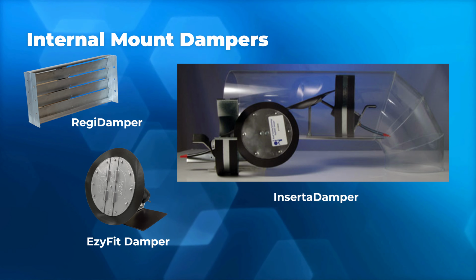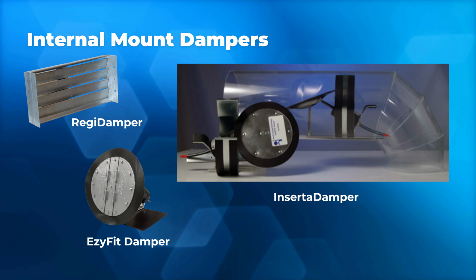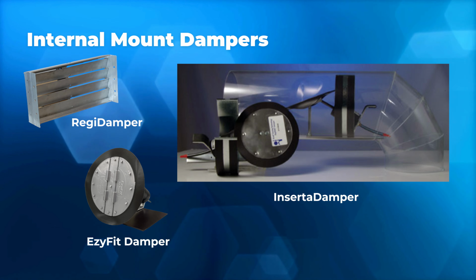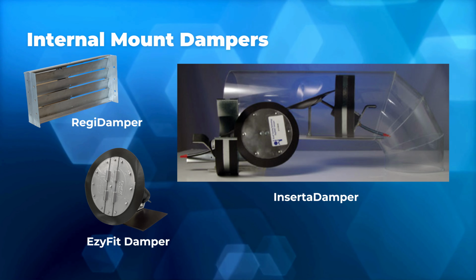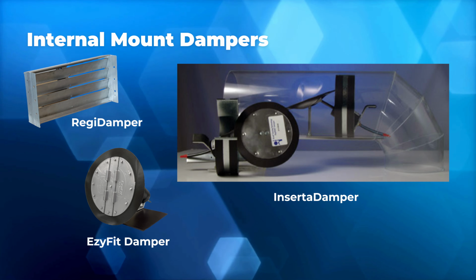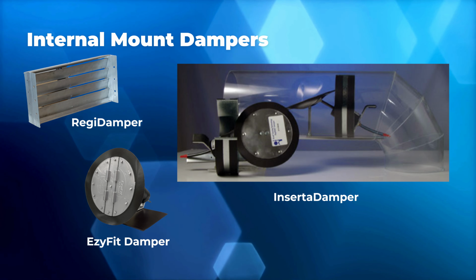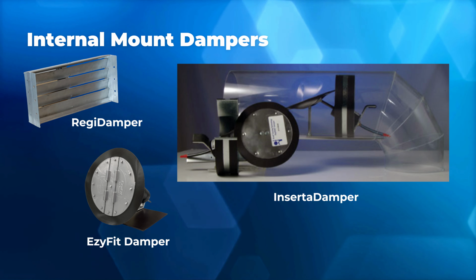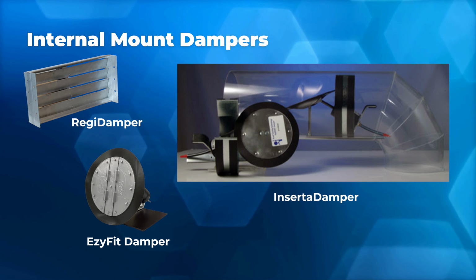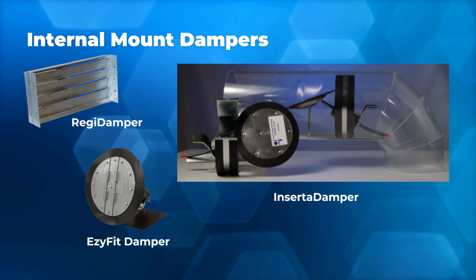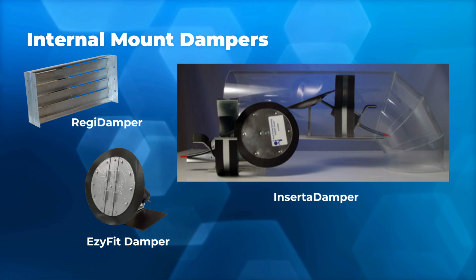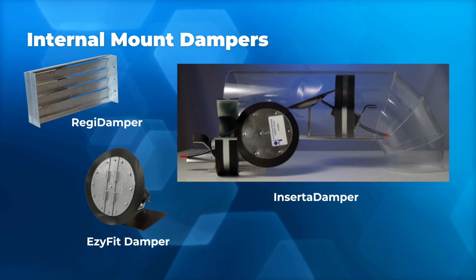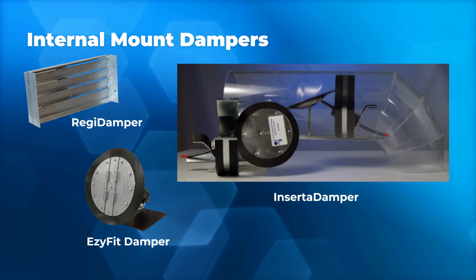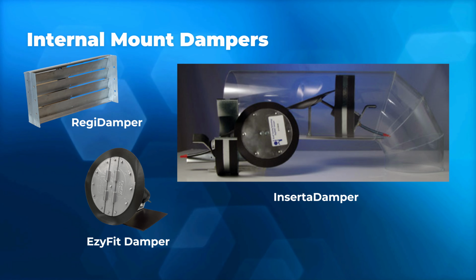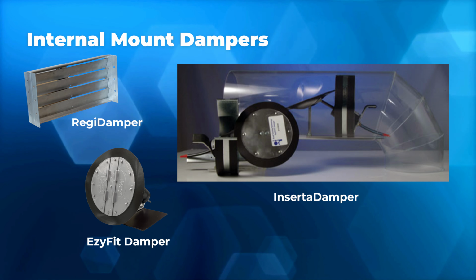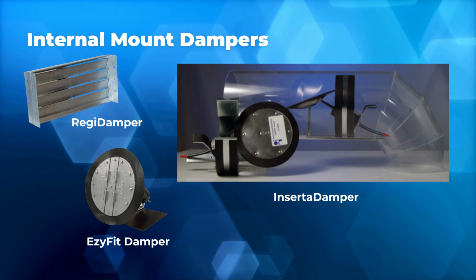Then the last option we have is our InsertaDamper. So this is going to be same thing if you have a slab home. If they have like an octopus run or something like that with the ductwork is really where this comes in. If they have clay pipe or PVC pipe for their ductwork is really where this one's going to excel. And essentially, if you have access to the main runs through your main trunk line, what you could do is insert this through there. So it's got a metal band on it that you squeeze in that holds it in place. So you squeeze the band, slide that in through the ductwork, and then that holds it in place, and then you'd run your tubing back that way.